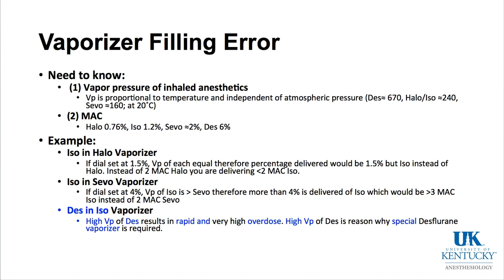What about anesthetic delivery at altitude? This requires you to know MAC as a partial pressure and what happens to vaporizers with changes in atmospheric pressure. An example first is the desflurane or Tec 6 vaporizer that's calibrated at sea level, and if you set it at 1 MAC or approximately 6% desflurane, it will deliver 6% at whatever altitude you're at.